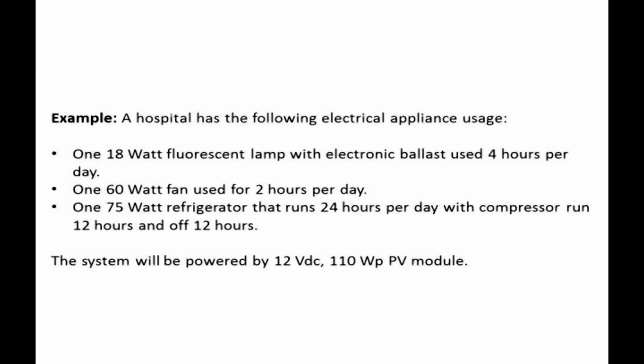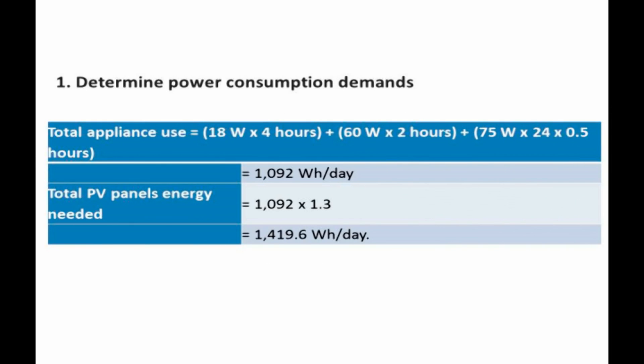Example: A hospital has the following electrical appliance usage — 18 W fluorescent lamp with electronic ballast used 4 hours per day; 60 W fan used 2 hours per day; 75 W refrigerator running 24 hours per day with the compressor running 12 hours and off 12 hours. The system will be powered by a 12 VDC, 110 Wp PV module. Step 1: Total appliance use = (18 W × 4 h) + (60 W × 2 h) + (75 W × 24 × 0.5 h) = 1,092 Wh/day. Total PV panel energy needed = 1,092 × 1.3 = 1,419.6 Wh/day.